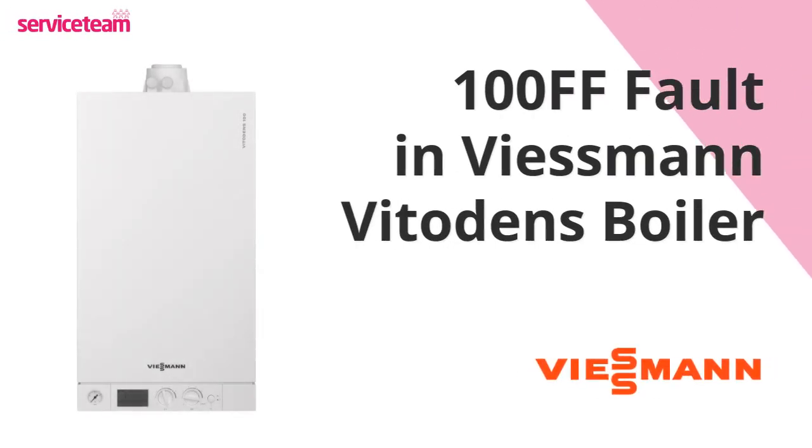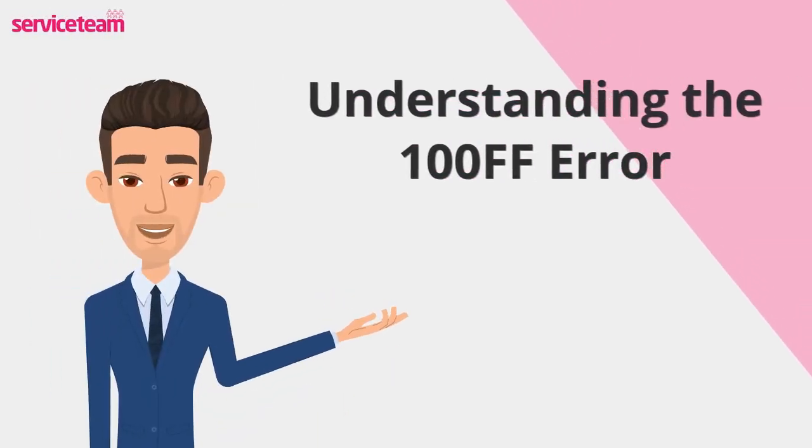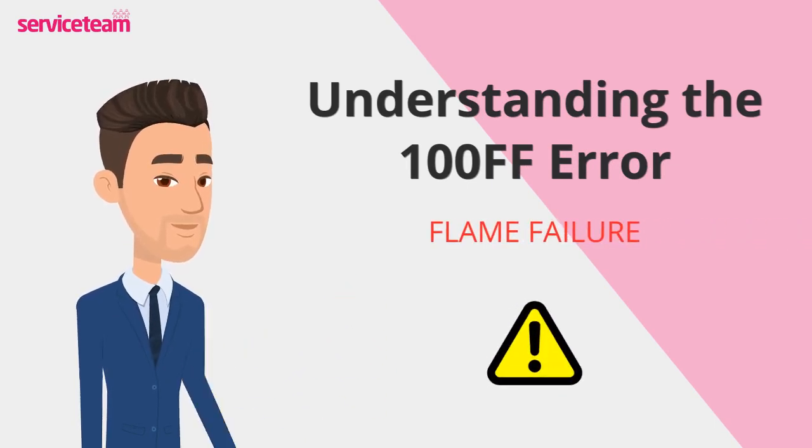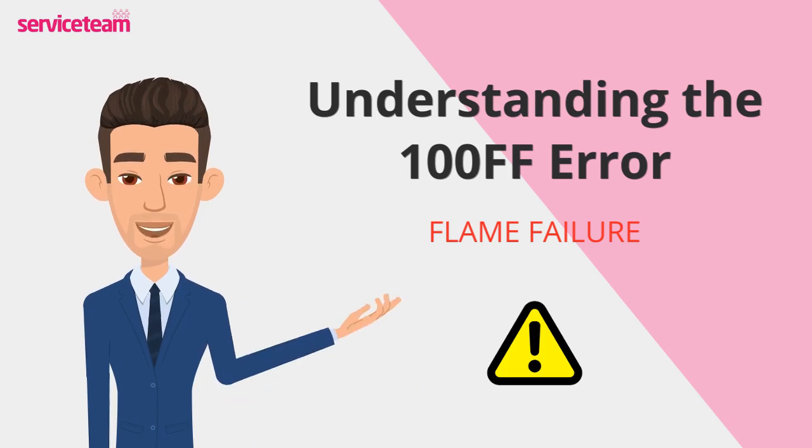Let's figure out how to resolve the 100FF error code on the Viessmann boiler. When your Viessmann boiler shows the FF fault code, don't worry. The FF code stands for Flame Failure. This simply means that your boiler tried to ignite but couldn't detect a stable flame, or the flame went out shortly after being lit.